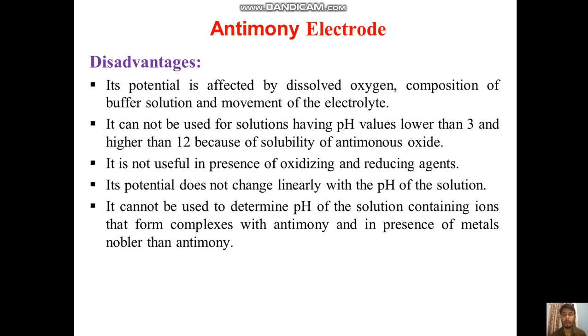Among the disadvantages: it cannot be used for solutions having pH lower than 3 or higher than 12. Its potential is affected by dissolved oxygen, the composition of the buffer solution, and movement of the electrolyte. It is not useful in the presence of oxidizing and reducing agents.